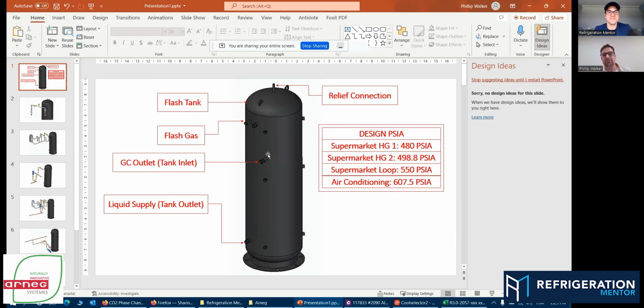Here's our inlet. We're coming down here, if you can see my cursor, coming down here from the gas cooler, going through a high pressure expansion device, coming right in here. And then here's my liquid outlet. So something really important, and this is going out to all the technicians listening right now, that we found over the years: stability is also insulation, and I can't comment enough on a good flash tank design in a mechanical room. You're going to need about 1-inch insulation.